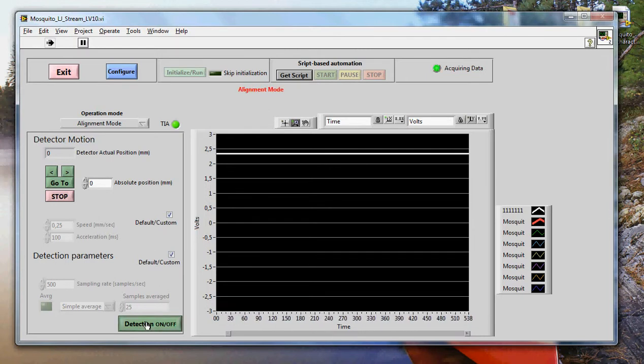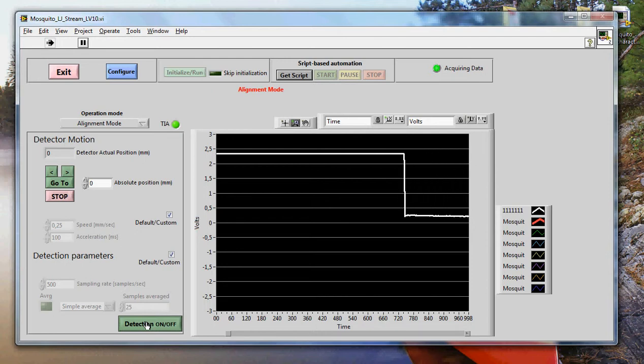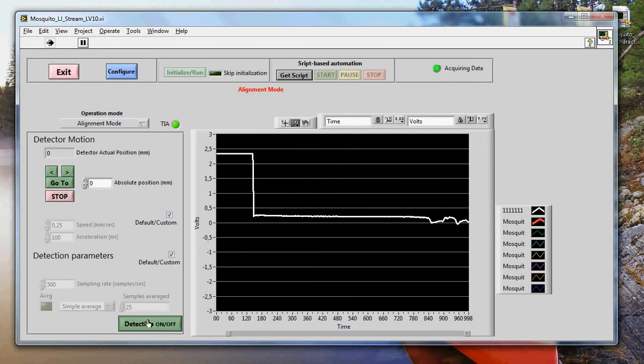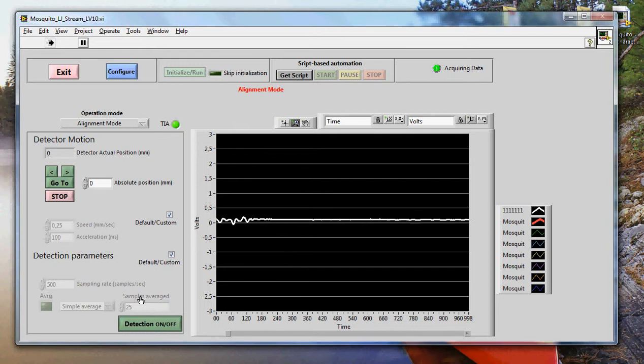Now this is where I put it on and off. And I move the fiber. And you see that the signal doesn't move. That means that the laser is not on. So I go on the box of the mosquito, turn the laser on. There you go. Now we have a signal which is live. I'm moving the fiber. So you're getting a live signal. So this is how you know if you forget to put the laser on and off.